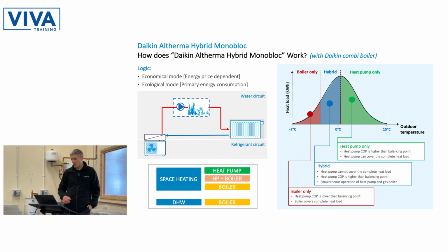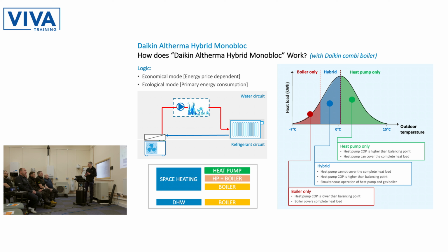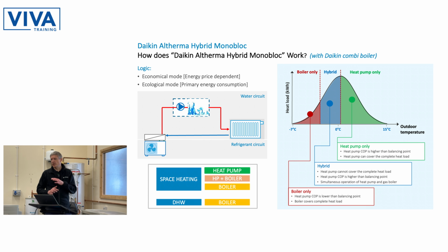So when will it operate the heat pump only? It will keep looking at this all of the time, and it will look at the coefficient of performance. So that's the efficiency of the heat pump, and it will look at which is actually more efficient at the moment in terms of cost. Is that the heat pump or is it the boiler? So where the heat pump is the most efficient, and when it can cover the complete heat load for the property, it will operate the heat pump only.